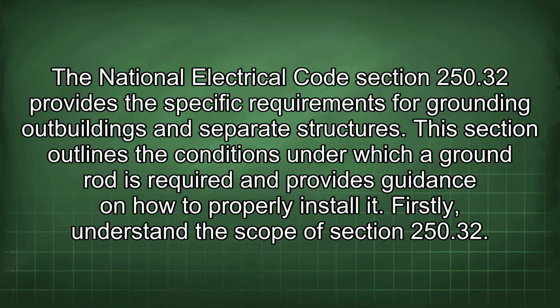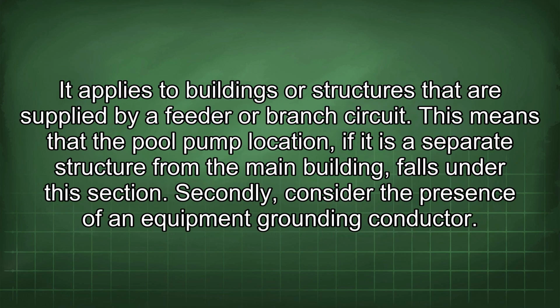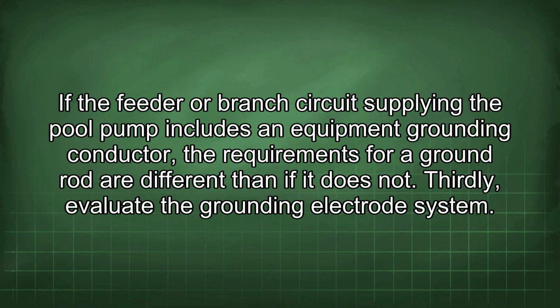Firstly, understand the scope of Section 250.32. It applies to buildings or structures that are supplied by a feeder or branch circuit. This means that the pool pump location, if it is a separate structure from the main building, falls under this section. Secondly, consider the presence of an equipment grounding conductor. If the feeder or branch circuit supplying the pool pump includes an equipment grounding conductor, the requirements for a ground rod are different than if it does not.